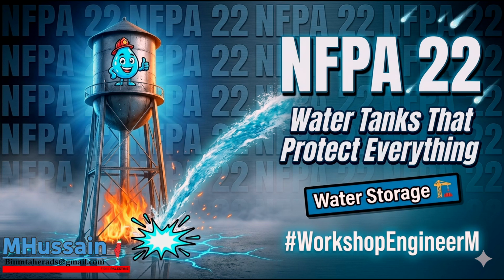Because if they get the ratio wrong, the physics fail. If they fill the water too high, there isn't enough room for the air, and the tank won't fully discharge. If they fill it too low, you don't have enough water to fight the fire. That raised arrow is a microscopic detail that guarantees the macroscopic physics of the tank remain accurate for half a century. The code is essentially forcing longevity into the physical hardware.